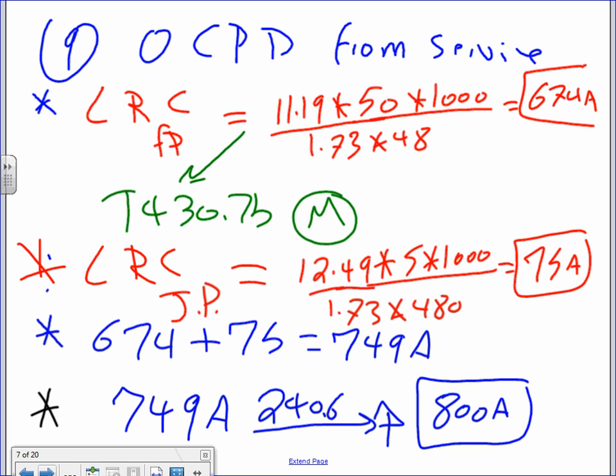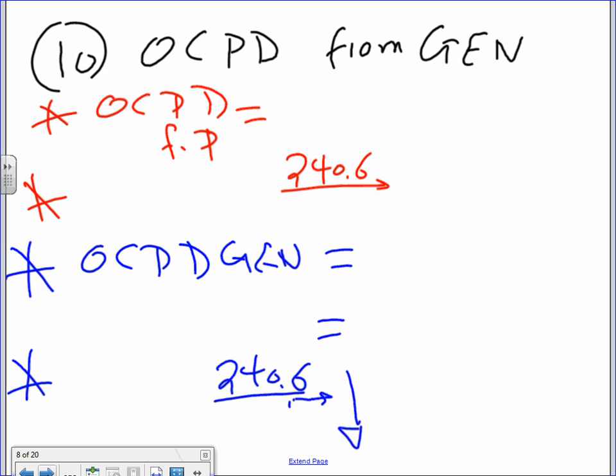Now let's go do it from the generator side. See how it's slightly different from the generator side. Okay, generator side, that's number 10. Generator side, guys, different. Look at that. You take 2.5. This is from the NEC code book for motors, from table 430.52. This 2.5 is from table 430.52. And you multiply it by the fire pump 65, and when you do that, that will get you a healthy 162.5 amps. Okay? That's step number 1.